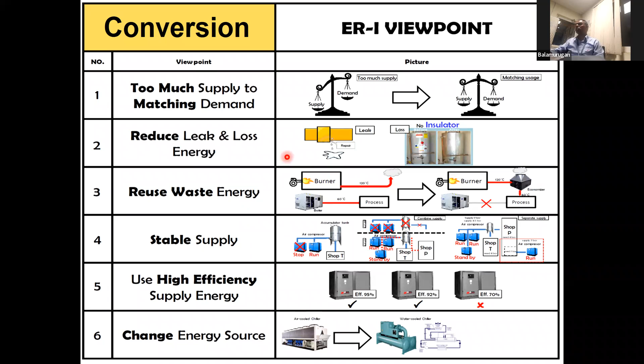This is a simple example: compressed air management system for energy reduction. The major issues we face in air compressor management are basically no data available for compressor efficiency. Nobody monitors the CFM on a daily basis unless an external auditor comes in to do the energy audit and measure supply CFM versus demand CFM. So usually no data is available. There's non-standardization of compressor standards by management, and no system for understanding optimum pressure equipment, leading to too much conversion and huge loss in the system.